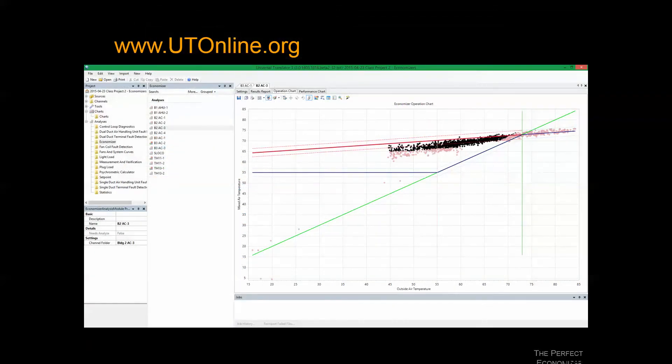That's the spreadsheet method to assess economizers and build the ideal profile. Software tools can also accomplish this — one example is the Universal Translator, which can import portable data logger data or building automation system trends and open an economizer analysis module to quickly show how actual performance stacks up.